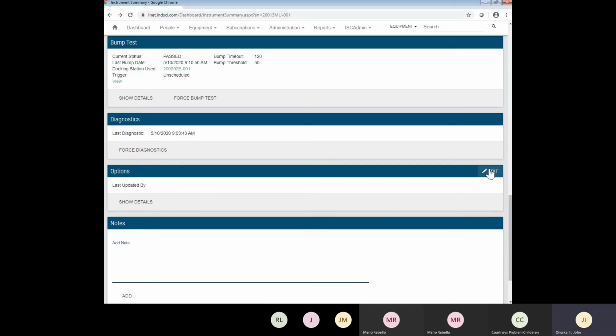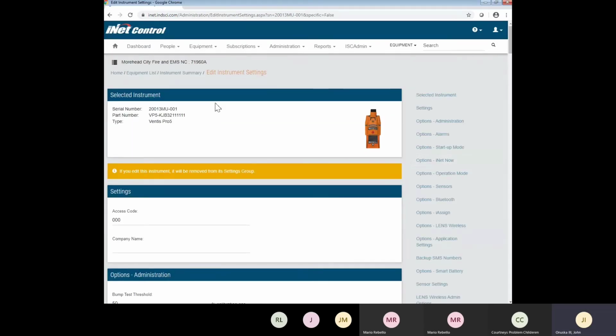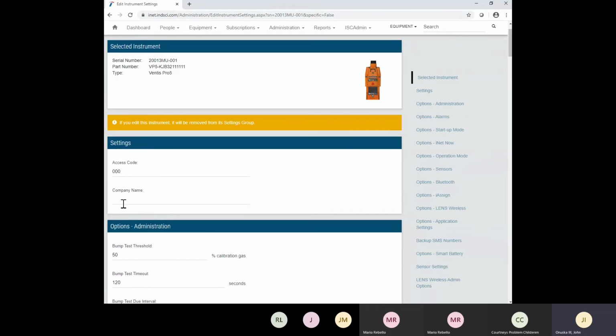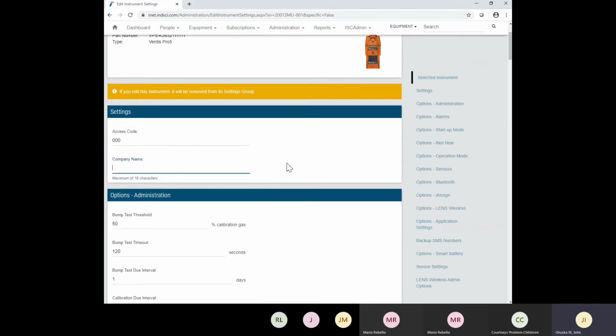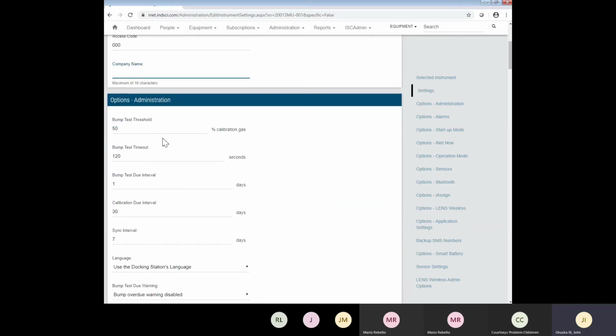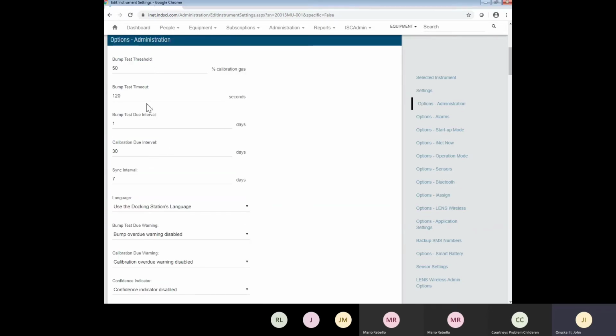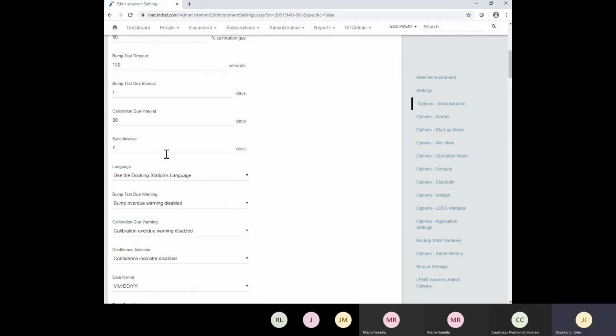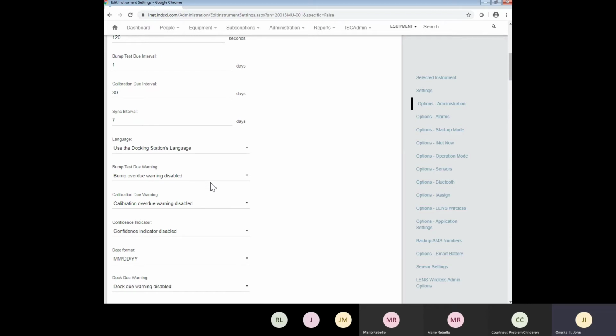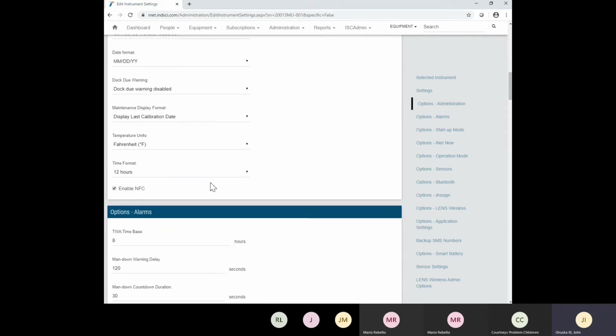Under options though, right here, if we click on edit, this is where we can get into all the options for the instrument. So you can put like your company name right there, what station you are, like station 1, station 2, whatever, and that will pop up whenever the instrument turns on. As you come down, here's where you can change all your bump test settings, okay, on the instrument itself. This is just for the warnings and everything else.